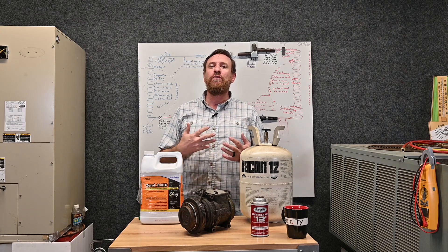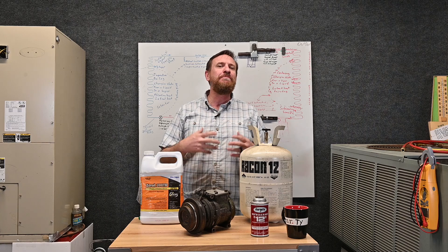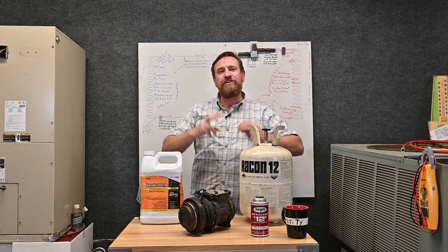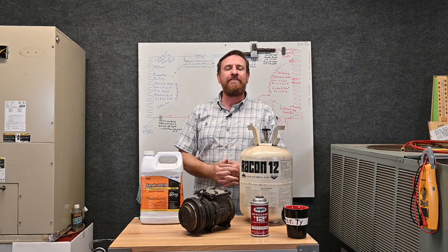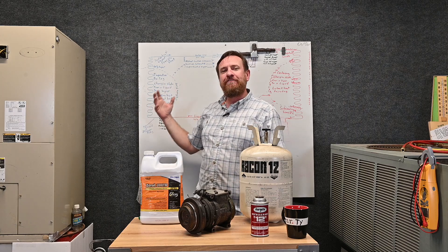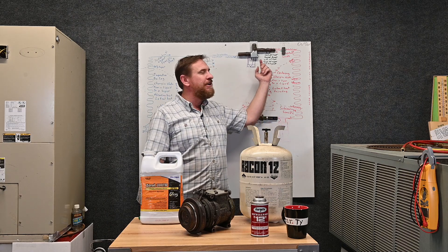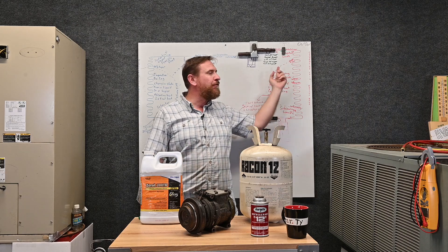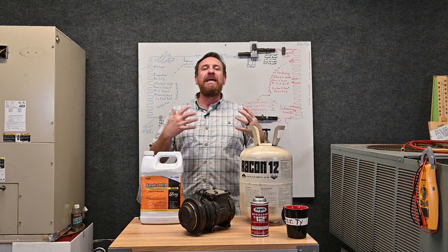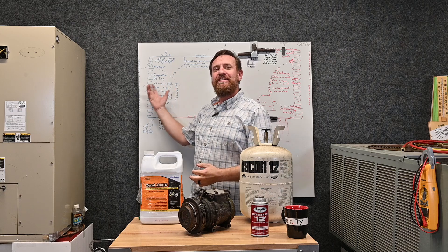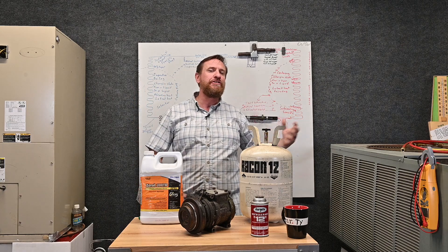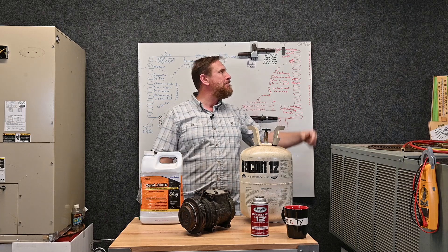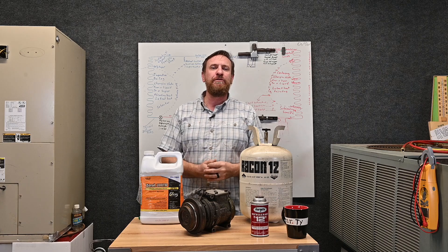These different refrigerants have different weights — their specific gravity is going to be different. Just because a refrigerant has a pressure that you like doesn't mean it's going to be absorbing the correct amount of heat. Different refrigerants have different weights, so it affects how much volume is going through that compressor — the volumetric efficiency. The size difference between a 410A and R22 compressor is quite different, even though we have the same saturated temperature and condensing temperature for a set of conditions. They design it that way by the metering device matching the compressor and how much volume that compressor is moving.